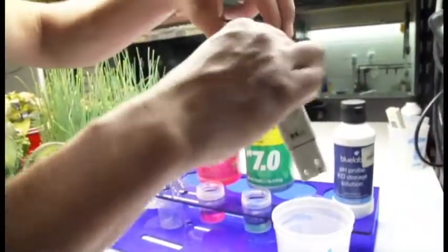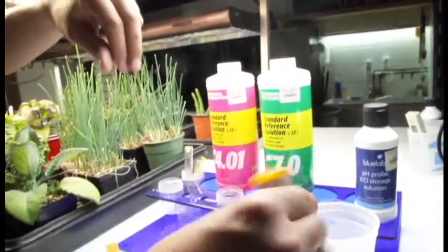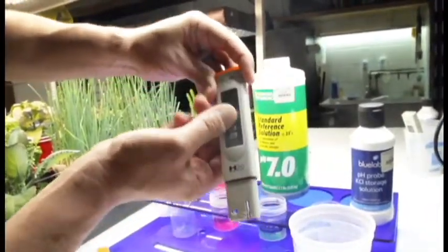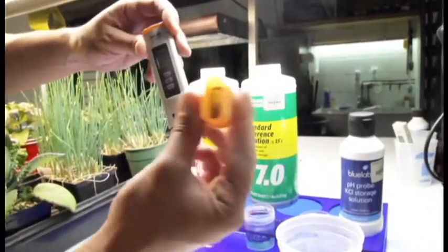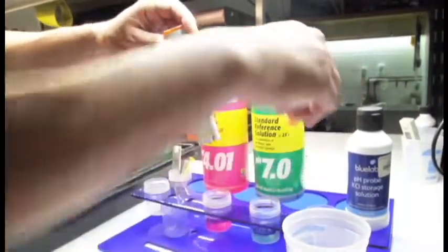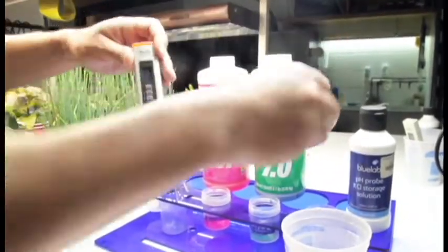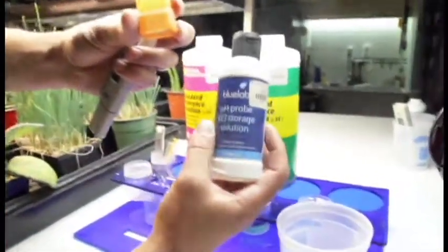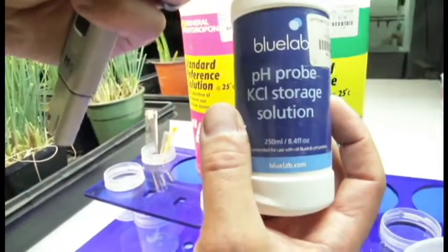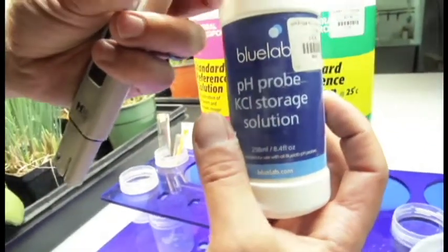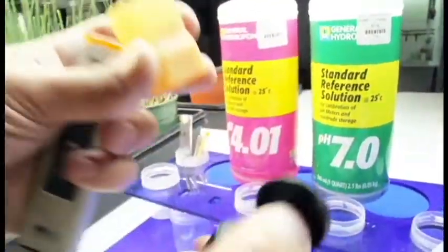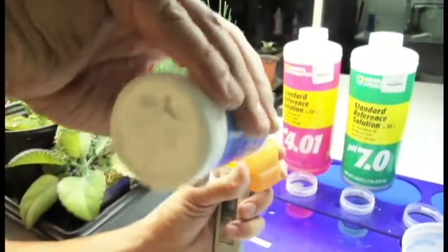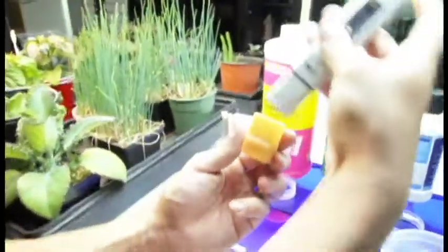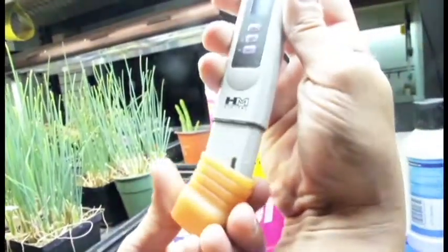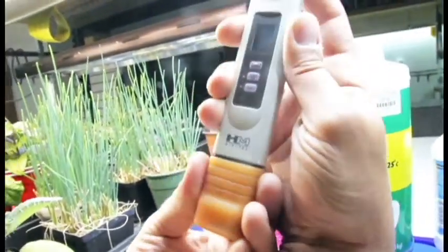Now when I'm done using it, or if I was just calibrating it, before I put it away, I'll turn it off. I made sure I rinsed it. Inside this cap is a little sponge. I like to squeeze out the old solution, which isn't going to be a lot, and then I use a pH probe storage solution to put into the cap while I'm storing it to keep the probe moist. So this is probably my favorite one. I only put in just a couple little drops, not a lot. Once it's in there, I can now take my meter and put the cap back on. I like to walk these silicone caps on since the probe is an osmotic membrane.